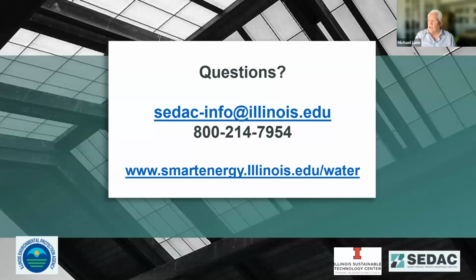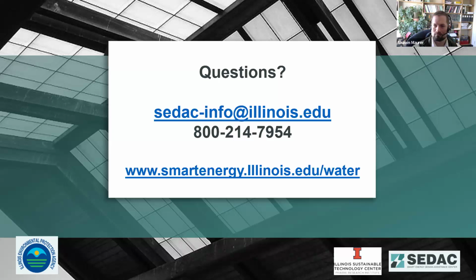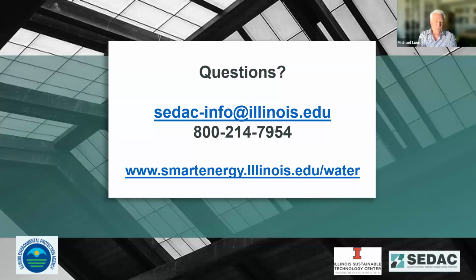So I see a lot of that going on, and people scheduling time to take care of these things. When we think about our plants and the huge investments we make in them, if you have a tens of million dollar plant, I see a lot of people giving up on these sensors because you have to maintain them. It's a $15,000 sensor that improves the efficiency of a $50 million plant. That's the part I see most neglected in a lot of plants, some of the instrumentation. We never used it, we just set our blowers on 6 and called it good, right?